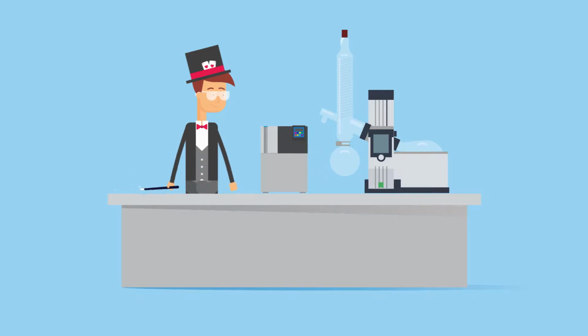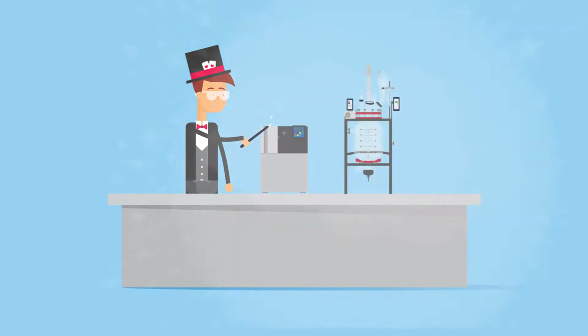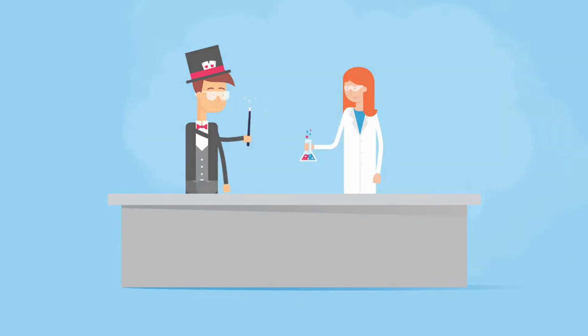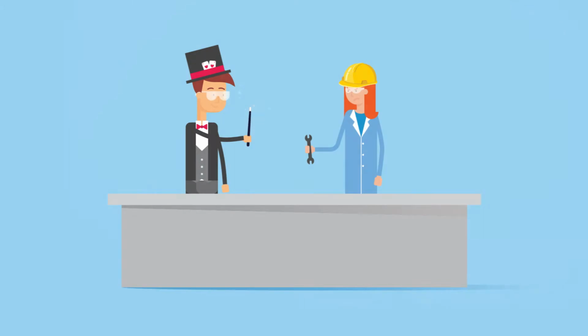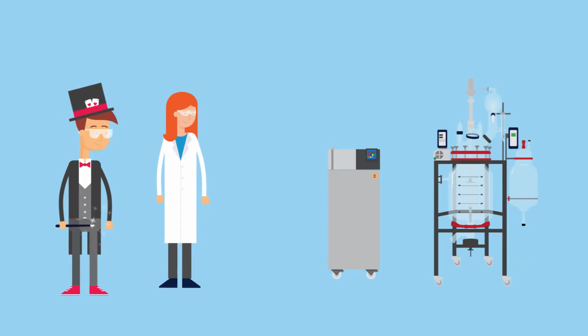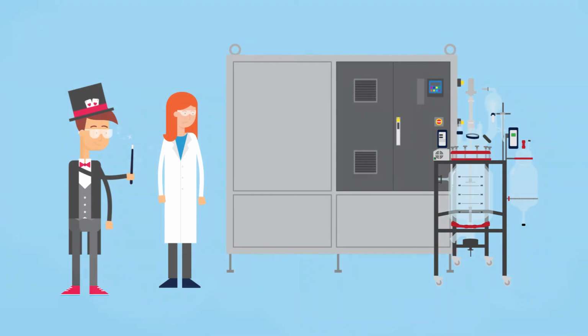Temperature control systems are required for a variety of applications and instruments, from evaporators to reactor systems, and find homes in a variety of labs, including research labs, clinical labs, and process labs. Circulators are available in a variety of sizes, and selecting the proper size adds to the economies of use.